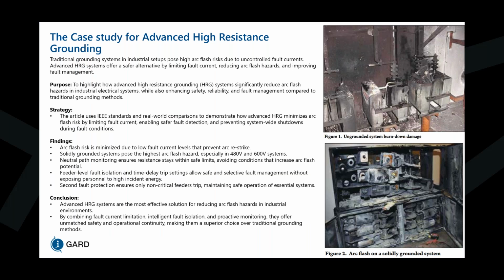There's also feeder level fault isolation and time delay trip settings with respect to second ground fault protection. If we see that there are two feeders experiencing faults on different phases, we can selectively trip the lower priority of the two feeders to make sure that we still have some continuity on one out of the two feeders, the one that is most important. The way we do this is our feeder modules have a 100 amp pickup, such that when that 100 amp threshold is passed, we automatically send a trip command to the lowest priority of the two seeing that 100 amps.